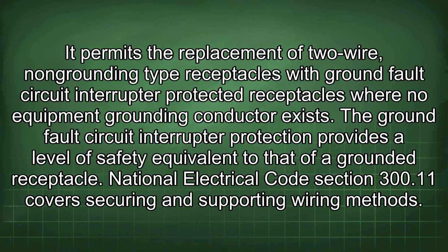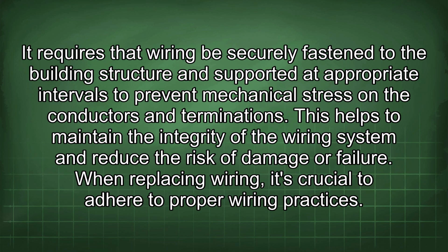It permits the replacement of two-wire, non-grounding type receptacles with ground fault circuit interrupter protected receptacles where no equipment grounding conductor exists. The ground fault circuit interrupter protection provides a level of safety equivalent to that of a grounded receptacle. National Electrical Code Section 300.11 covers securing and supporting wiring methods. It requires that wiring be securely fastened to the building structure and supported at appropriate intervals to prevent mechanical stress on the conductors and terminations. This helps to maintain the integrity of the wiring system and reduce the risk of damage or failure.